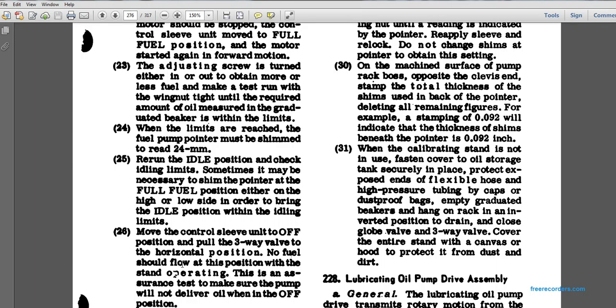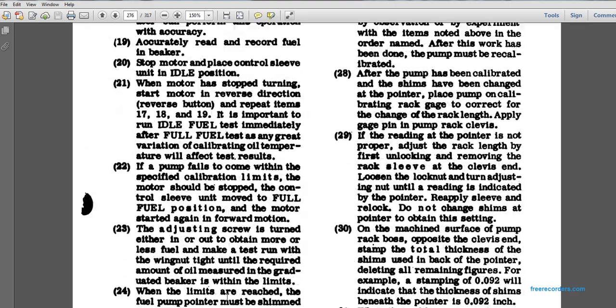Move the control sleeve until the position is off. Pull the three-way valve into the horizontal position. No fuel should flow into the beaker with the standard operation. This is an assurance test to make sure that the pump will not deliver oil when in the off position.